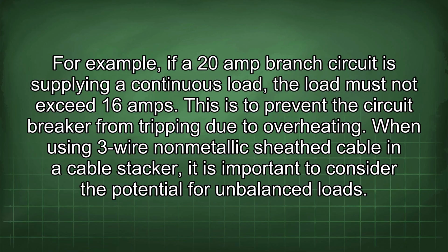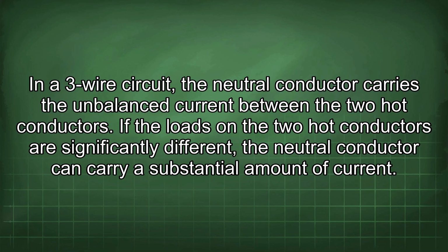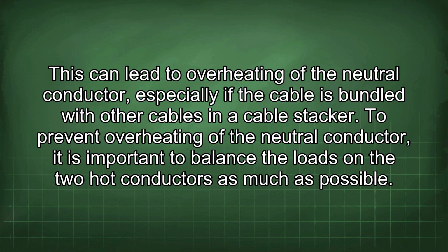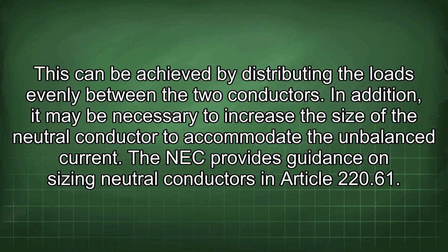When using 3-wire non-metallic sheath cable in a cable stacker, it is important to consider the potential for unbalanced loads. In a 3-wire circuit, the neutral conductor carries the unbalanced current between the 2 hot conductors. If the loads on the 2 hot conductors are significantly different, the neutral conductor can carry a substantial amount of current. This can lead to overheating of the neutral conductor, especially if the cable is bundled with other cables in a cable stacker. To prevent overheating of the neutral conductor, it is important to balance the loads on the 2 hot conductors as much as possible. This can be achieved by distributing the loads evenly between the 2 conductors.